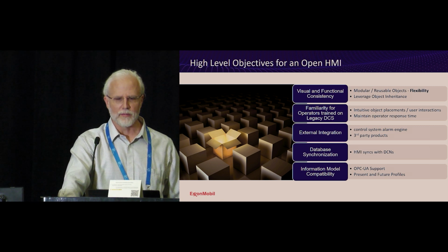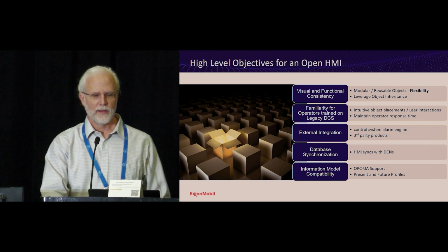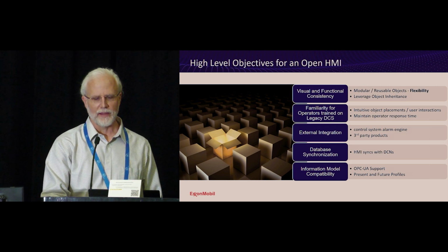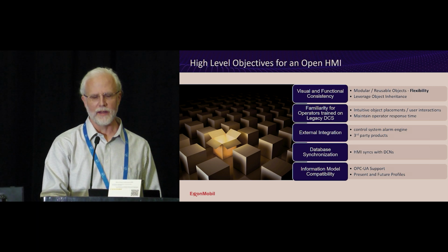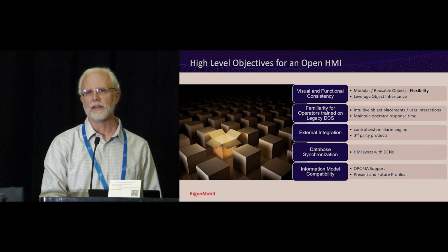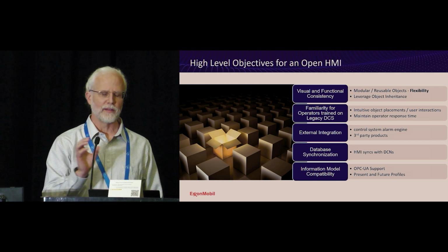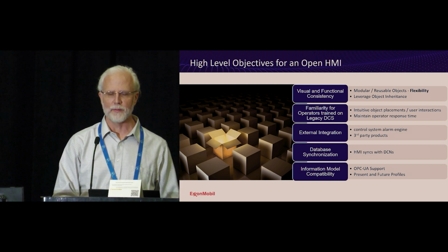But I think really the most important piece that I'm going to keep coming back to is that this whole thing is built on open standards, and the open process automation standards define an OPC UA information model. As long as you're designing your HMI to be built on that foundational information model, this is the piece that's going to enable you to reuse this HMI on systems regardless of what the hardware is. As long as it's consistent with those standards, you should be able to use it as a drop-in.